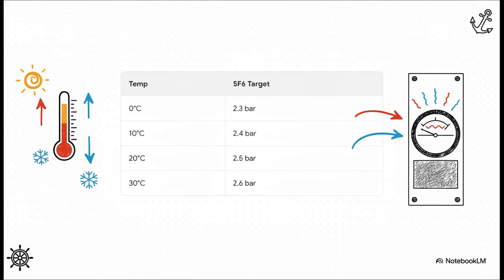The standard filling overpressure is 2.5 bar? Sure, but that's precisely calibrated for 20 degrees Celsius. As a marine engineer, you've got to recalculate based on the ambient heat. If it drops to 0 degrees, you fill to 2.3 bar. At 10 degrees, 2.4 bar. At 20 degrees, there's our standard 2.5. But if you're in a sweltering room at 30 degrees Celsius, your target climbs to 2.6 bar. The gas shifts, so your targets have to shift with it.